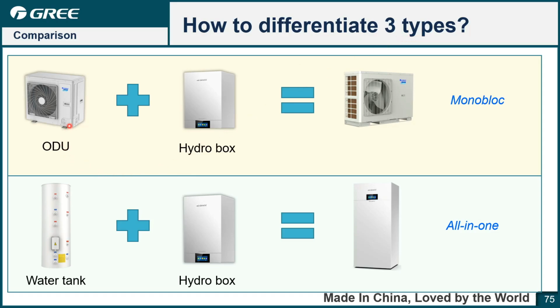For the regular split type, the outdoor unit, water tank and the hydro box are independent. However, if we put the hydro box and outdoor unit together, then you get the monoblock, which means the hydro box is integrated in the outdoor unit. And if you put the hydro box and the water tank together, then you get the all-in-one. Here is the hydro box, here is the water tank. So actually for the monoblock and the all-in-one, the design is more compact, and a lot of customers want this kind of design just for the installation and the appearance.